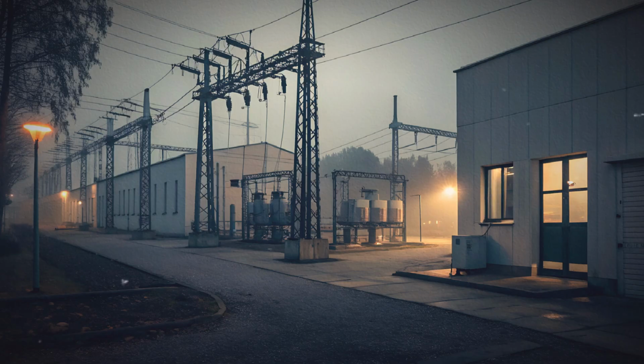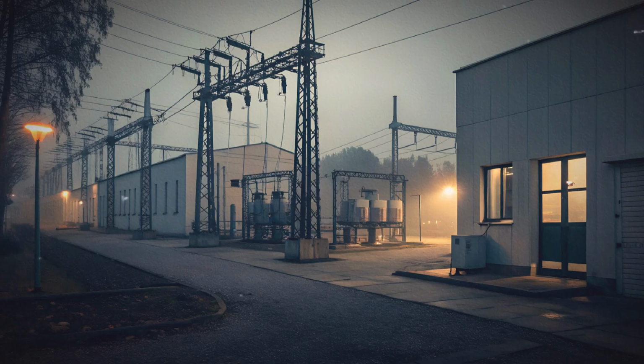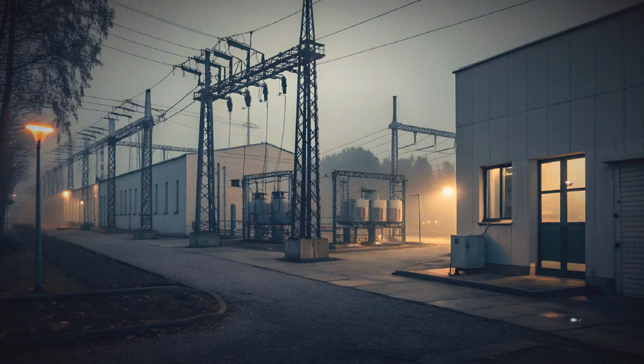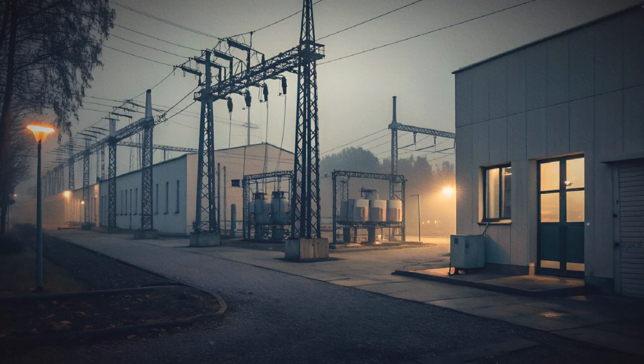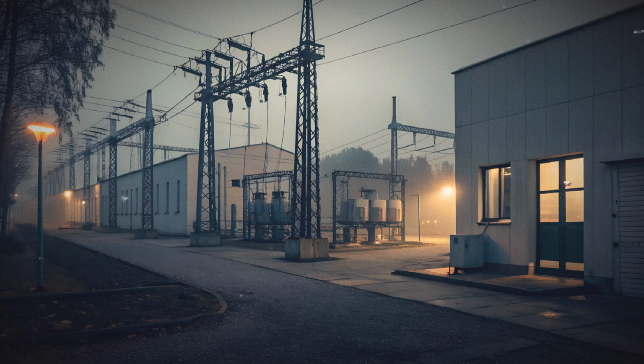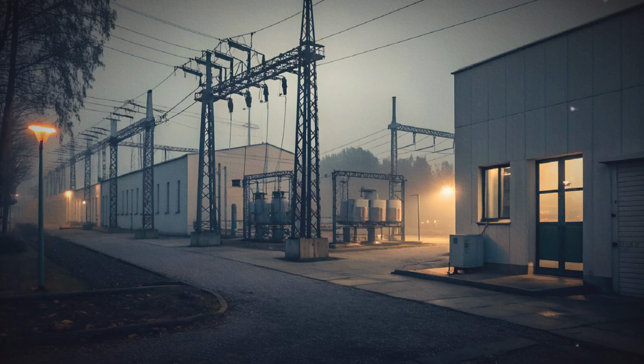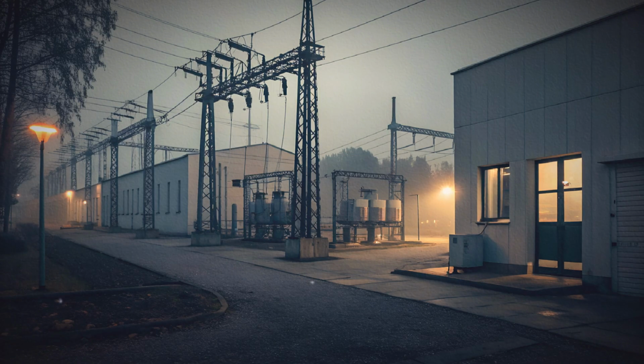Switching equipment is essential in a substation. Circuit breakers can interrupt current flows quickly. Disconnect switches provide visible isolation for maintenance. Bus bars collect and distribute power inside a substation. Different bus arrangements exist, such as single bus, double bus, and breaker-and-a-half configurations. These arrangements influence redundancy and ease of maintenance. Redundancy allows parts of a substation to be taken out of service without interrupting supply to connected areas. Switching also supports the reconfiguration of networks to respond to faults or planned outages.